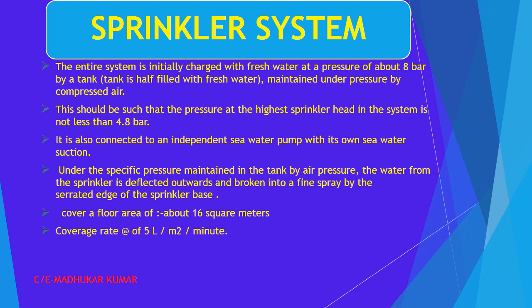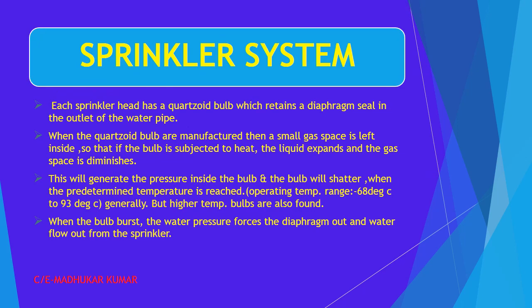Okay, the coverage area as per the SOLAS requirement: the coverage area of the floor is about 16 square meters, and the coverage rate is approximately 5 liters per square meter per minute. Now we can see over here the sprinkler head is attached with a quartzoid bulb which is retaining a diaphragm seal, and this diaphragm seal is holding the valve system, and it holds the water in the pipeline because all the time the pipeline is being pressurized.